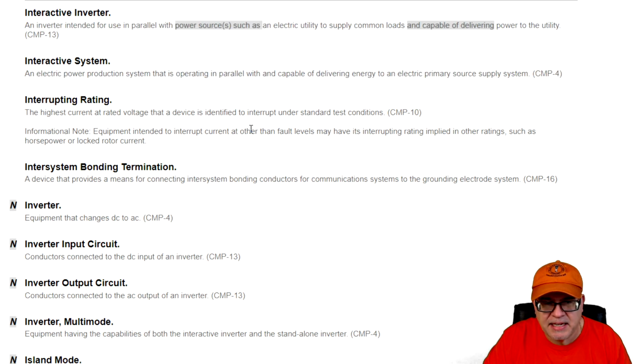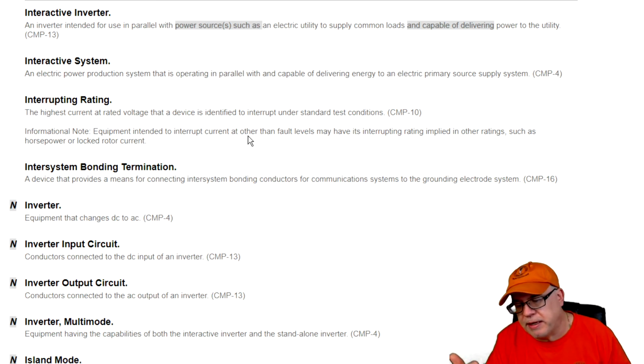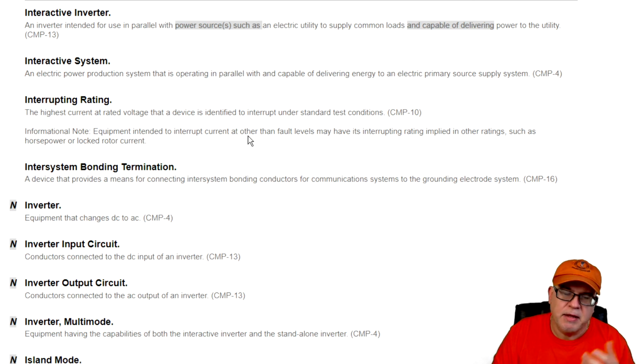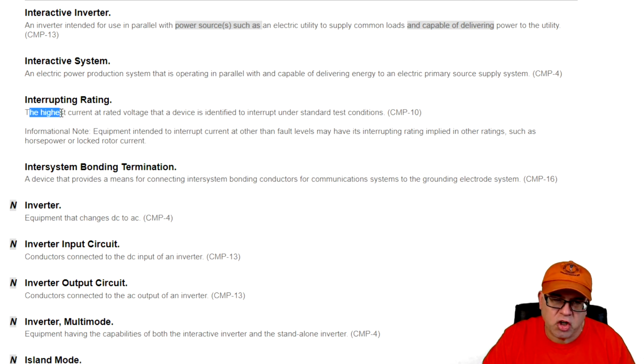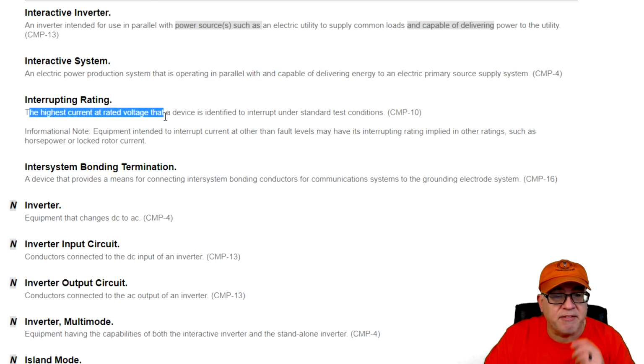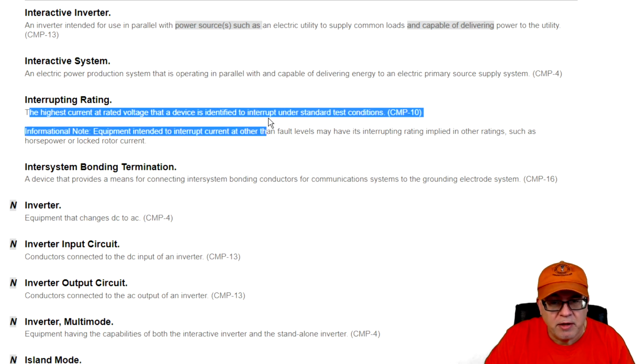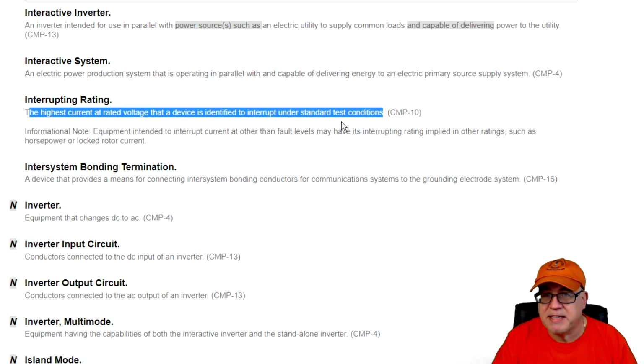110.9 and 110.10 talk about short circuit current ratings and interrupting ratings, okay? Where the short circuit current rating is for equipment, the IR rating is the value of the device. And what is interrupting rating? It is the highest current at rated voltage that a device is identified to interrupt under standard test conditions. So it's been tested. So if you have a circuit breaker and it's a 10,000 IR interrupting rating, then it's been evaluated to handle current at that voltage. What if it's a 120 volt circuit breaker? It can handle current up to 10,000 amps, all the way up to that current, up to that voltage's test rating. So that's why it got the 10,000 amps.